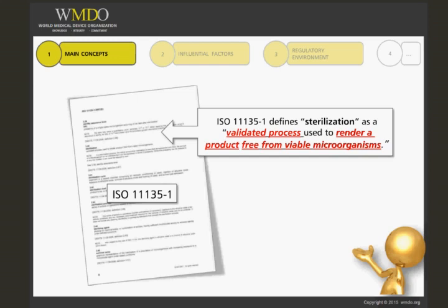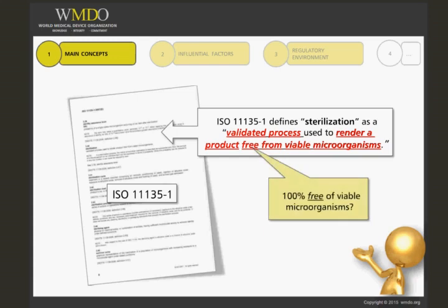A sterilization process will never guarantee that a product is free of viable microorganisms — it will always give a probability. An important concept to keep in mind is: the higher the probability of the device being free of microorganisms, the more reliable the sterilization process.